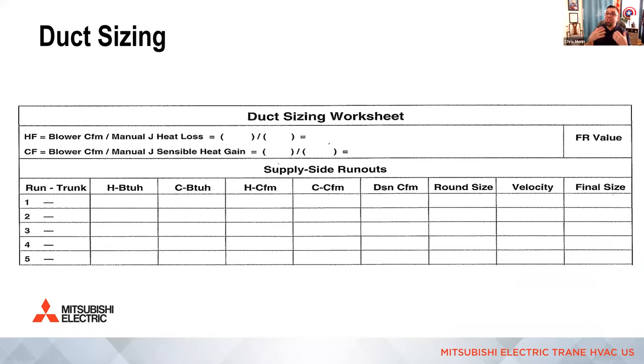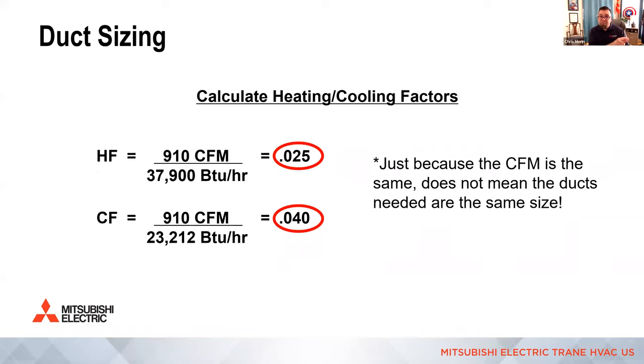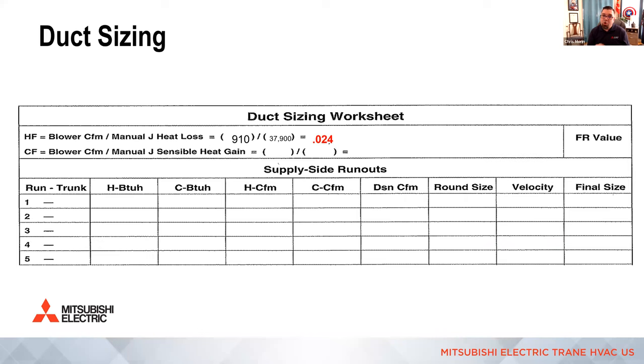And then when we size these runs, the same process applies. I'm going to walk through this. It's going to be a little quick, but that's because I want to spend time on the design. We already walked through how to size runs, okay? I just want to make sure you can see it. But even with a longer list, the same process applies. So we would take our heating CFM and divide it by the heat loss for that first floor in this example, which was 37,900. Remember, that comes off of your Manual J version 8 approved software. Three decimal points is the max you want to go. In this example, it was 0.025. Of course, with this heat pump, it's the same volume of air and cooling, less BTU needed, and sensible only. Remember, latent is taken out at the coil, so only sensible for our duct design: 23,212. When we do the math, it's 0.040. So those two numbers get transferred over to our duct sizing worksheet.